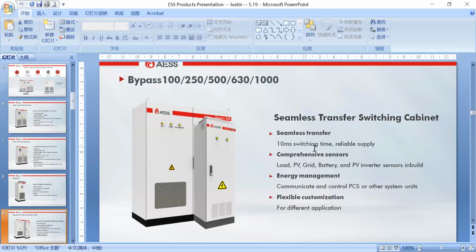Okay, how to choose our bypass? Okay, from the rated power, we can see it's similar to our PCS. So when we choose our bypass, the rated power of the bypass has to be equal to or more than the rated power of the PCS. Okay, for example, if we use PCS 500, for the bypass you need to choose at least 500 or more than 500. Maybe you can choose 630. Okay, it has to be equal to or higher than the rated power of our PCS. Okay, and how many bypass do we need in application? It really depends on how many PCS we have.